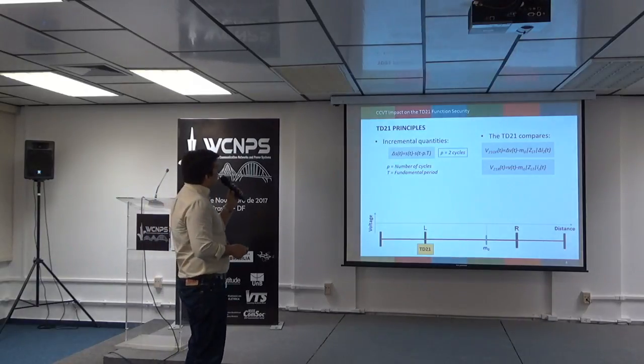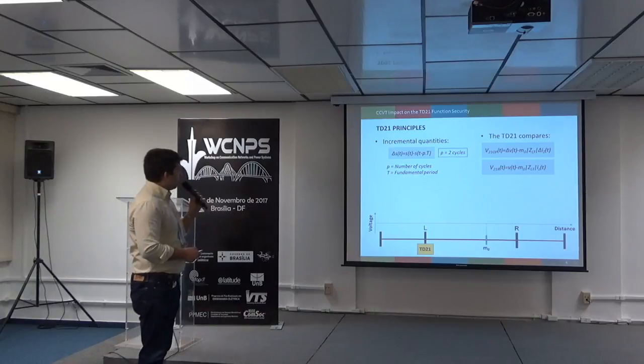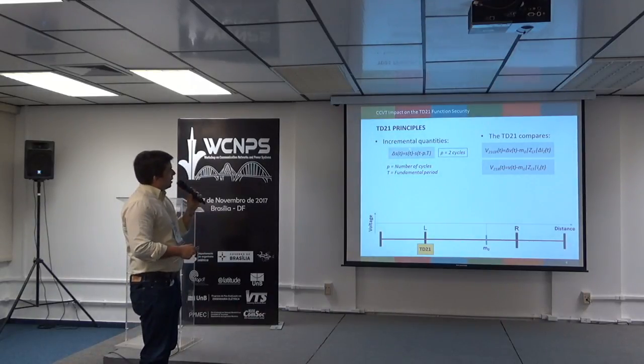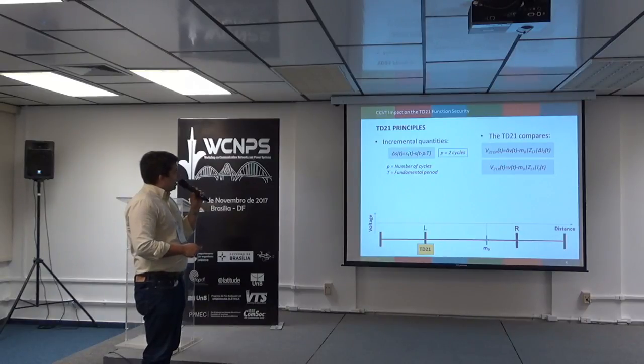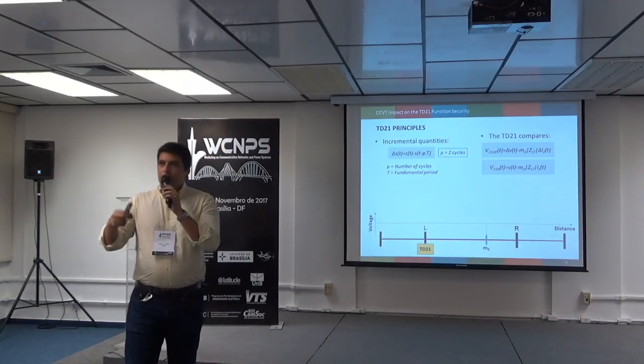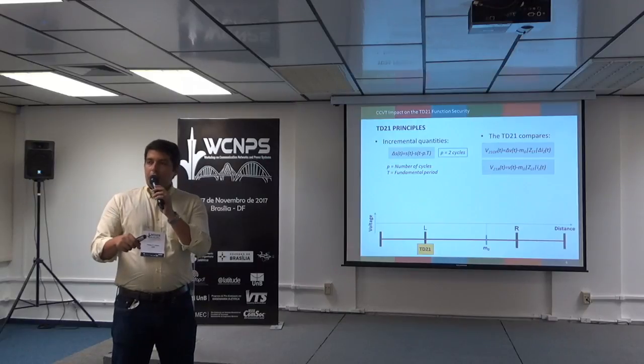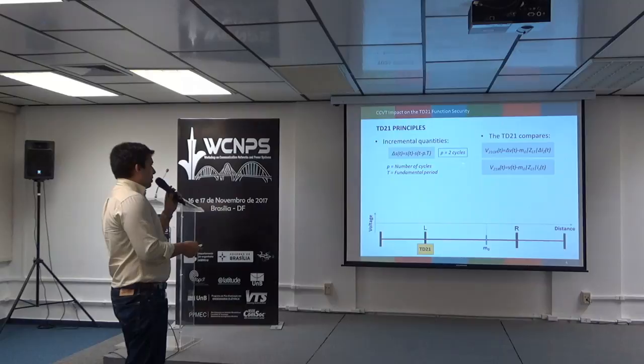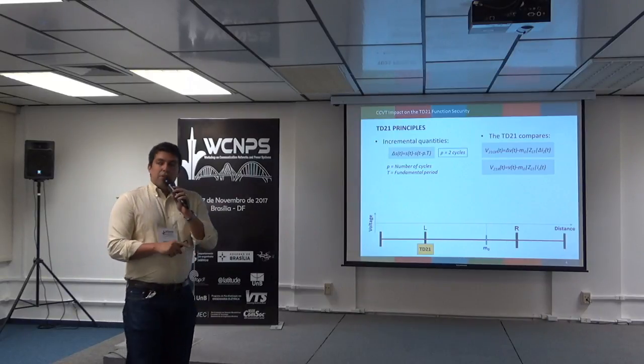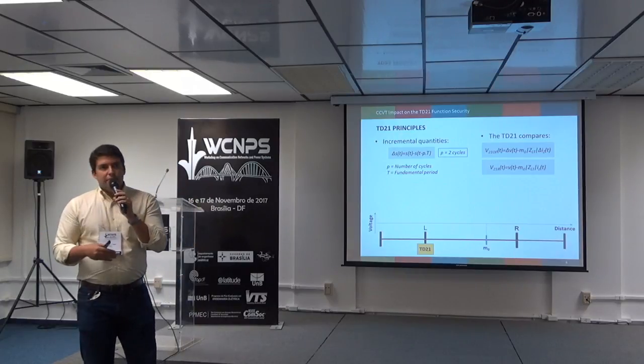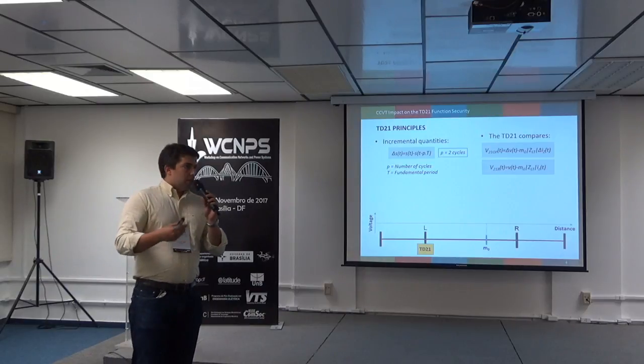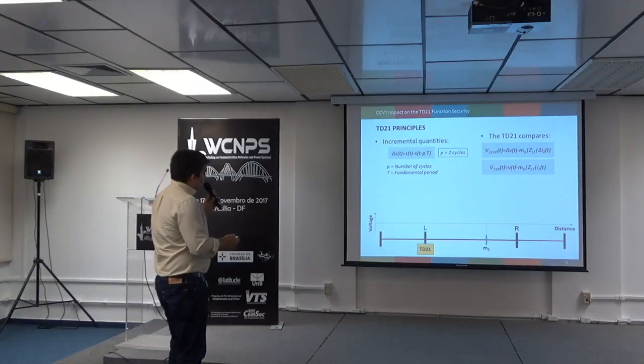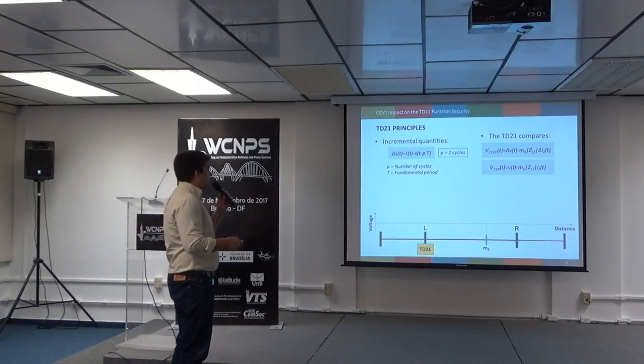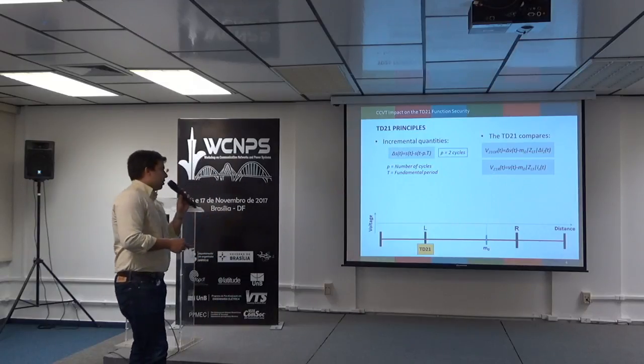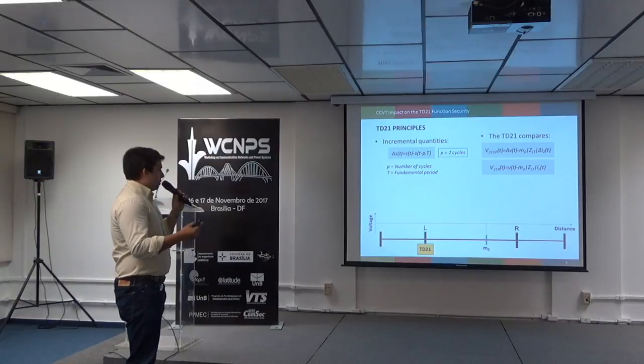Just to illustrate the main principles of the TD21 function, let's assume that incremental quantities are computed using this formula here, where s(t) is the actual instant sample. So we take the difference between the sample and the P cycles delayed sample. In this paper, we considered P equal to 2 cycles. So this function is valid only during these 2 cycles. After that, the phasor-based functions must be used because the incremental quantities are no longer valid. By using voltage and current incremental quantities, we can compute an operating and a restraining voltage. The operating voltage is based on the pure fault circuit, and the restraining voltage is based on the pre-fault circuit. And as a result, we have something like this.